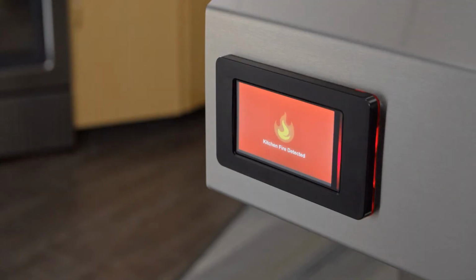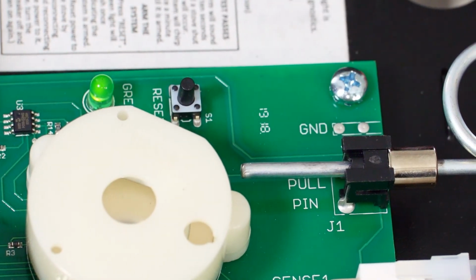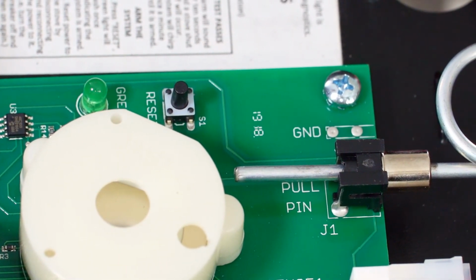The gas reset fault will appear when the gas disconnect does not properly reset upon attempting to unlock the range. The kitchen fire detected message will occur when the temperature reaches 216 degrees Fahrenheit or if the remote pull station has been pulled. After successfully passing all 6 diagnostic tests and pressing the reset button on the fire suppression control board, the board will display a solid green light for 2 seconds, and then the unit will enter into fire detect mode, or in other words, ready mode.